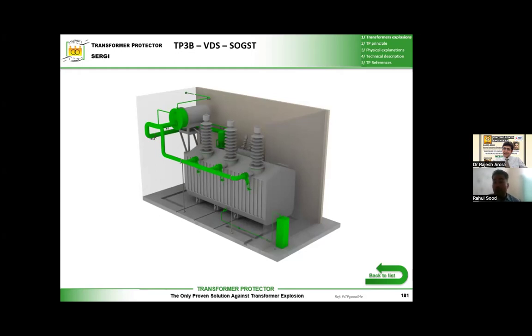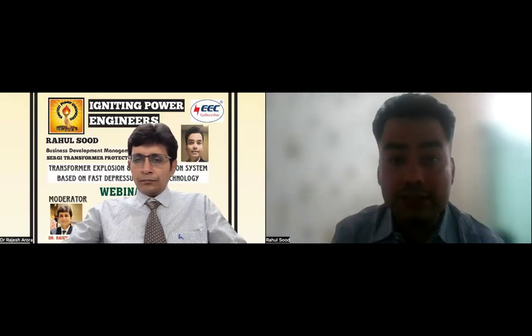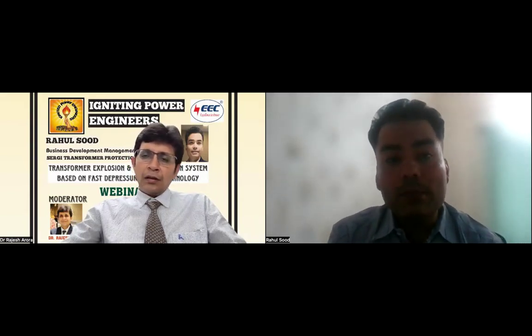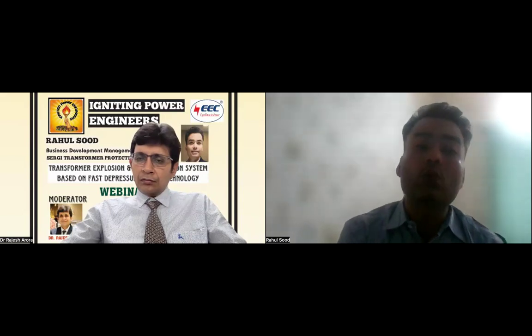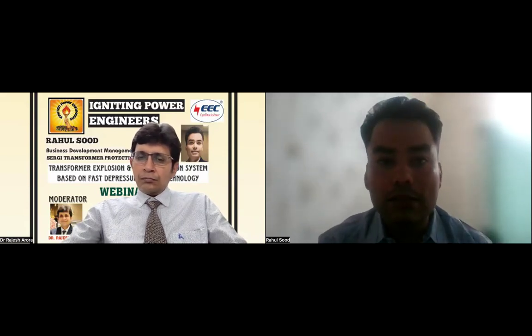Okay, it's a very good question. In fact, I thank you for this question. Now, our system, as I said, is not dependent on any signals to activate. We activate mechanically. The rupture disk works on the increase in pressure. When the pressure reaches the calibration level of the rupture disk, the rupture disk bursts. We provide double burst indicators over this rupture disk. The signal from this rupture disk can be taken to trip your transformer, to the circuit breakers to trip your transformer. Do you have provision for that? Yes, exactly. We give that, and the moment our system activates, the transformer is isolated, and then it moves further.